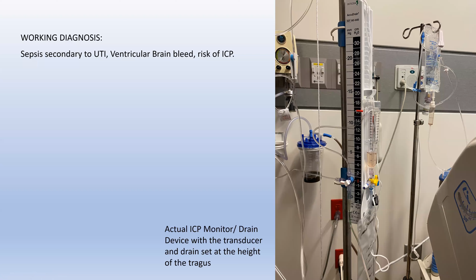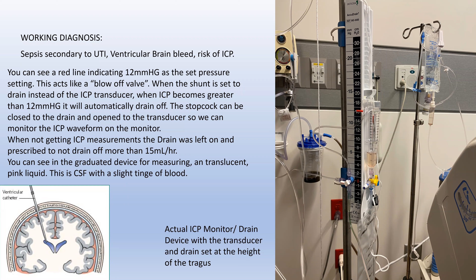So one thing, actually, I'm going to go back really quick. If you're doing transports with these, it's very important to shut off the flow to the patient prior to moving the patient. Because if this is not properly level to the patient, you could massively increase or decrease their intracranial pressure purely based on where this is sitting. So again, it's important to shut it off and then you'll turn it back on once you can level it out. Also poses an additional issue with flight when things can become very imbalanced very quickly.